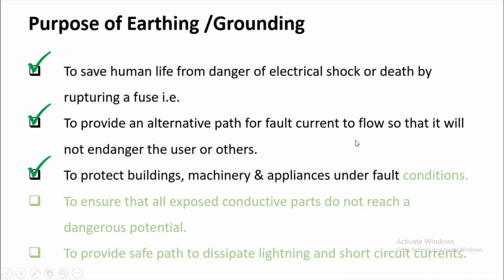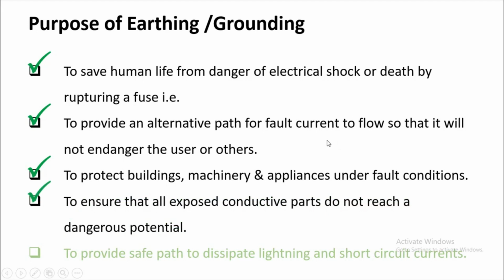To protect buildings, machinery, and appliances under fault conditions. To ensure that all exposed conductive parts do not reach dangerous potential. To provide a safe path to dissipate lightning and short circuit currents. So it is also protecting the building and appliances from lightning, not only from short circuits.